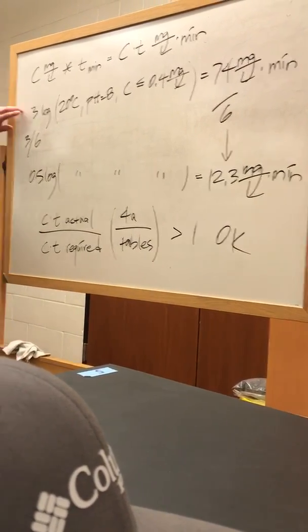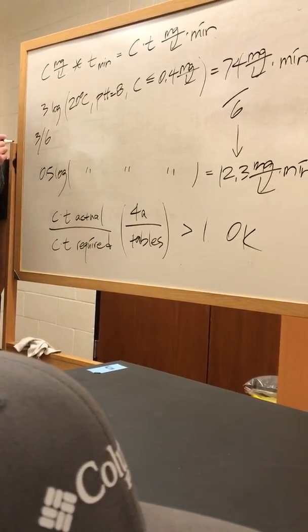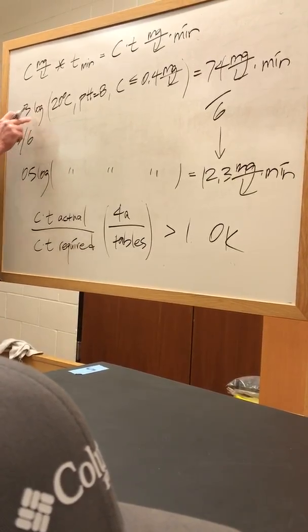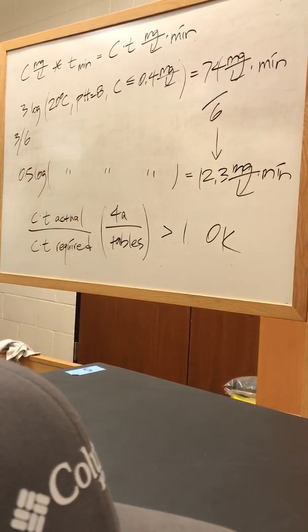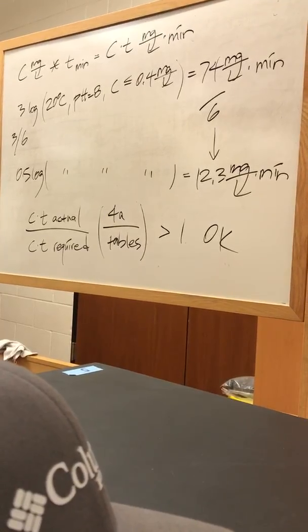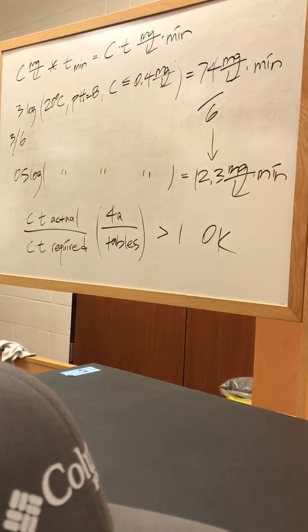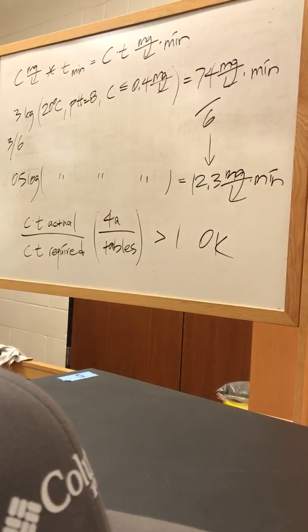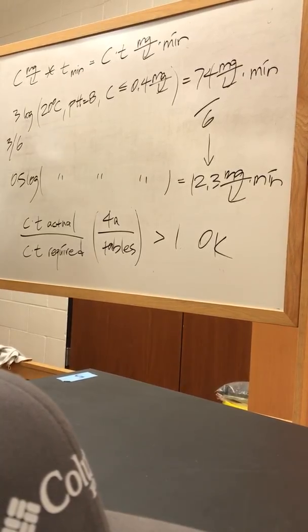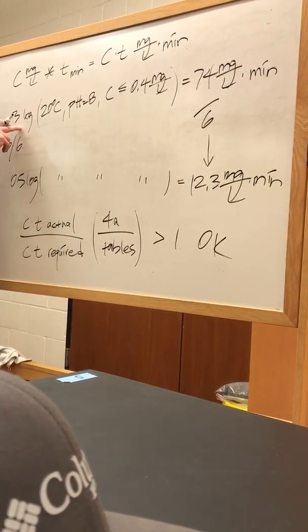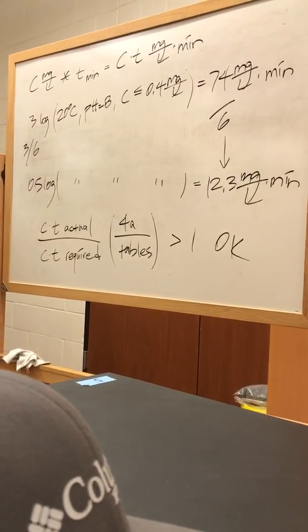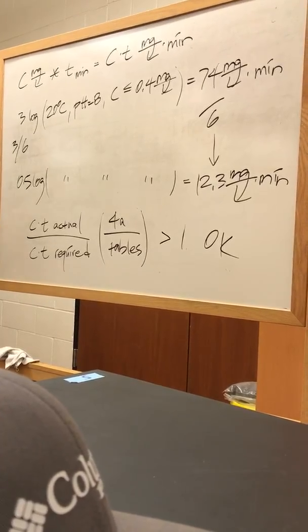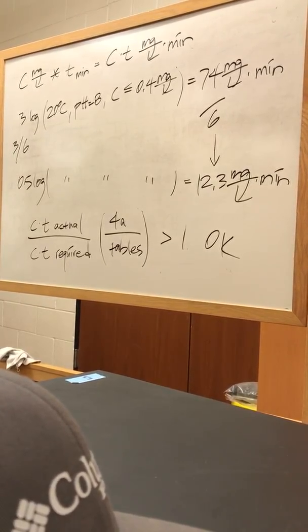So this log, remember, is the ratio of organisms, right? 3 log removal of the initial concentration of microorganisms, which is what we're using as our removal parameter. And it could be total fecal coliform, like we did in that coliform experiment. 3 log removal would be 99.9%. Okay? So from the initial to the final, you've lost 99.9%.